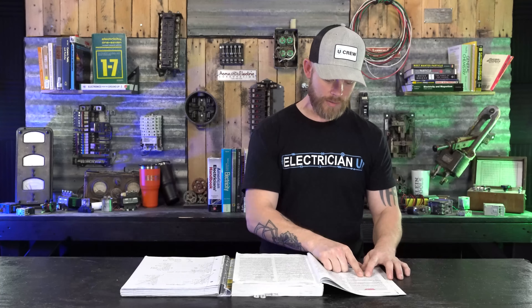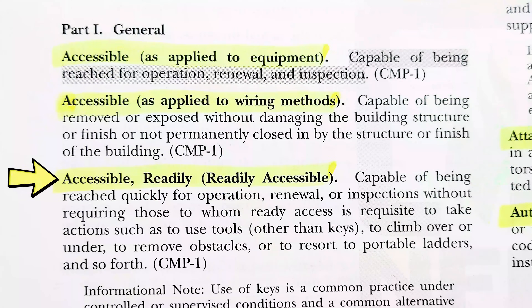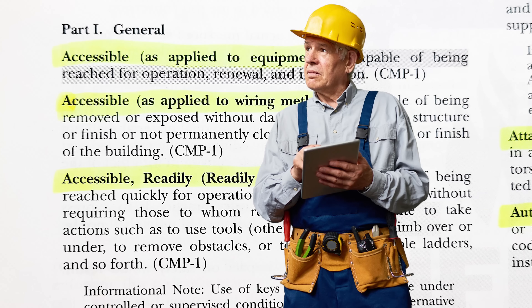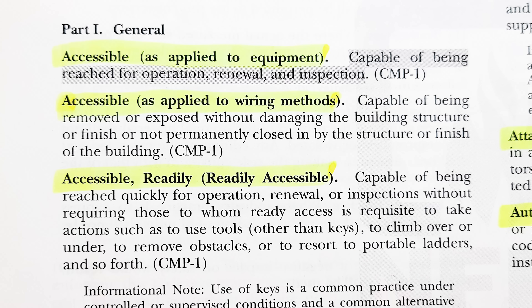Next up we have 'readily accessible.' In code it's still under the A's — 'accessible, comma, readily.' Readily accessible means capable of being reached quickly for operation, renewal, or inspections without requiring those to whom ready access is requisite — like an inspector or someone who works at a place — to take actions such as use tools other than a key to open something.